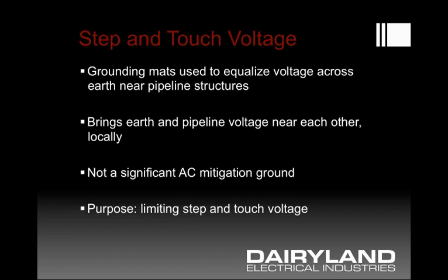This isn't going to be a really fantastic low-resistance AC mitigation ground. This kind of mat is usually sitting in gravel — high-resistivity fill on purpose to further limit the person away from the voltages seen on the mat. That means it won't be a very low-resistance ground, and it doesn't need to be. Its main purpose is step and touch voltage protection, not actual voltage reduction relative to earth.